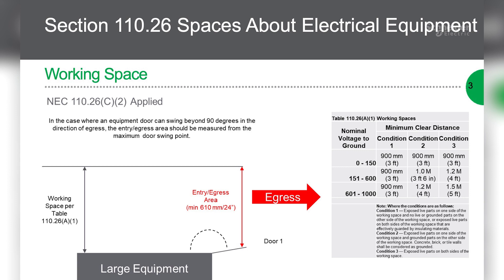For example, if we take a 480-volt switchboard with a grounded concrete wall at the edge of the working space, that's a Condition 2 condition for Table 110.26, requiring three and a half feet or 42 inches of working space clearance. If we take a standard switchboard door that's 30 inches wide and opens 120 degrees, we're protruding 26 inches into that working space, leaving only 16 inches — no longer meeting the 24-inch egress path requirement, so the electrical room has to get bigger.